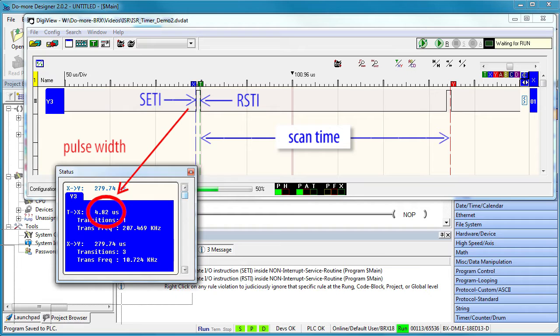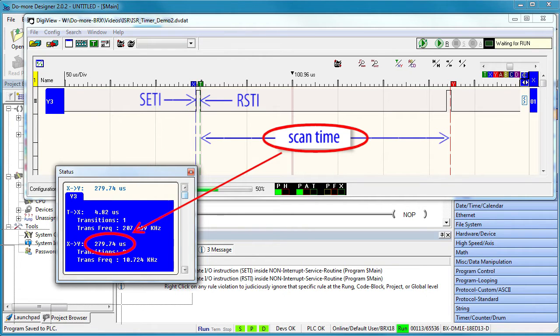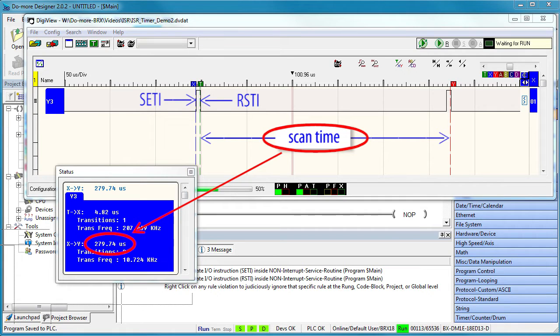Looks like it takes just a couple of microseconds to do that. But look at this - the scan time takes about 280 microseconds. Why does the scan take so long if all we are doing is toggling a bit?